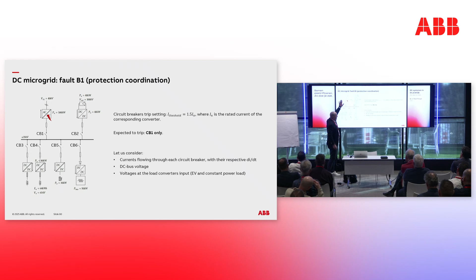Maybe you don't. But then I was thinking, okay, here's the thing. If I do that, and I have a redundant system here, everything is going to feed into the fault. We see it here in the simulation, where the black current is the current flowing into the active front end, and it's essentially a summation of all the currents from the grid. The problem is, I could, in theory, wait for everything to discharge and reach complete zero, and then start opening my electromechanical device. But the electromechanical device will take 40 milliseconds to open. No load is going to ride through for 40 milliseconds. And if I designed it for such a long ride-through time, I would defeat the purpose of having DC, because I would need a huge capacitor at that load to supply that kind of energy.